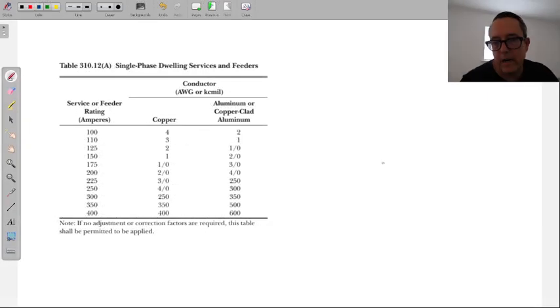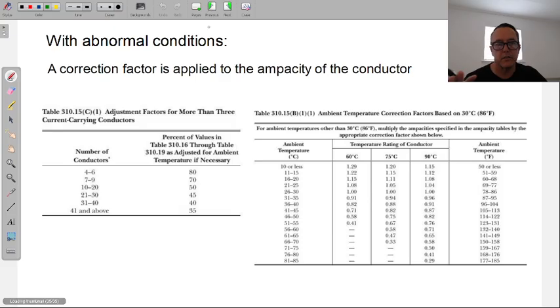So we did, like, whatever, we had 1,000 amps, and we said how many parallel 3, how many parallel 2, how many parallel 4, and we selected a bunch of wires in that regard. But again, if no abnormal conditions exist. If abnormal conditions exist, we always apply the abnormal conditions table, always. All right, because this can get a little confusing when you're selecting wires, especially when you're sitting in front of an exam and you're going, oh, which one was this one? Do we just do this? And when do we use this table, etc. All right, questions?